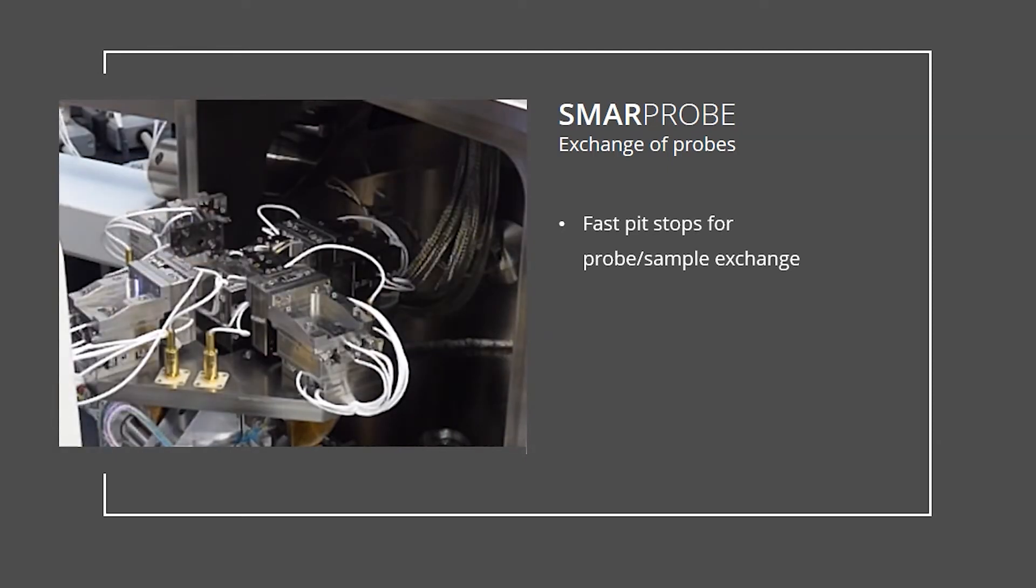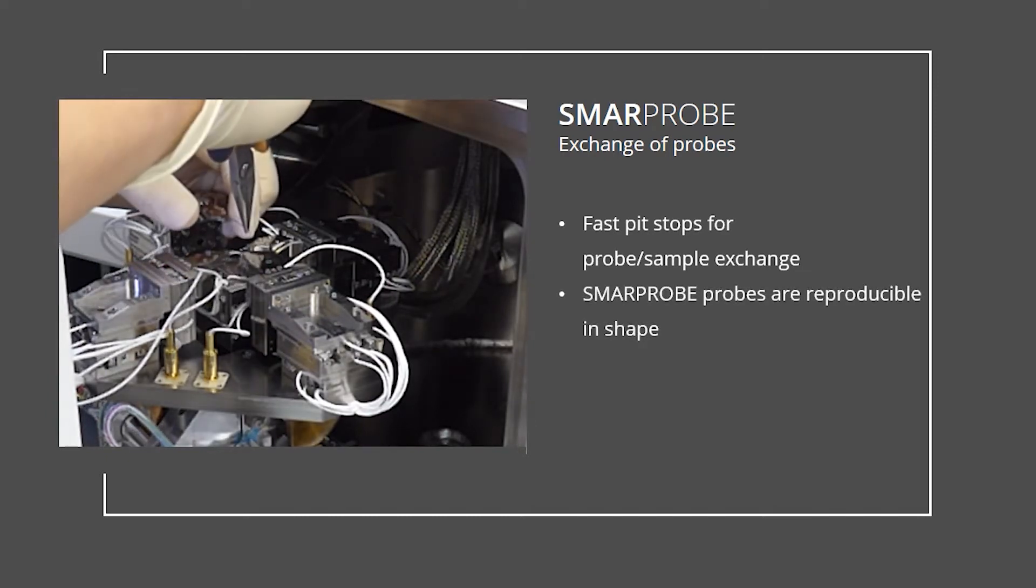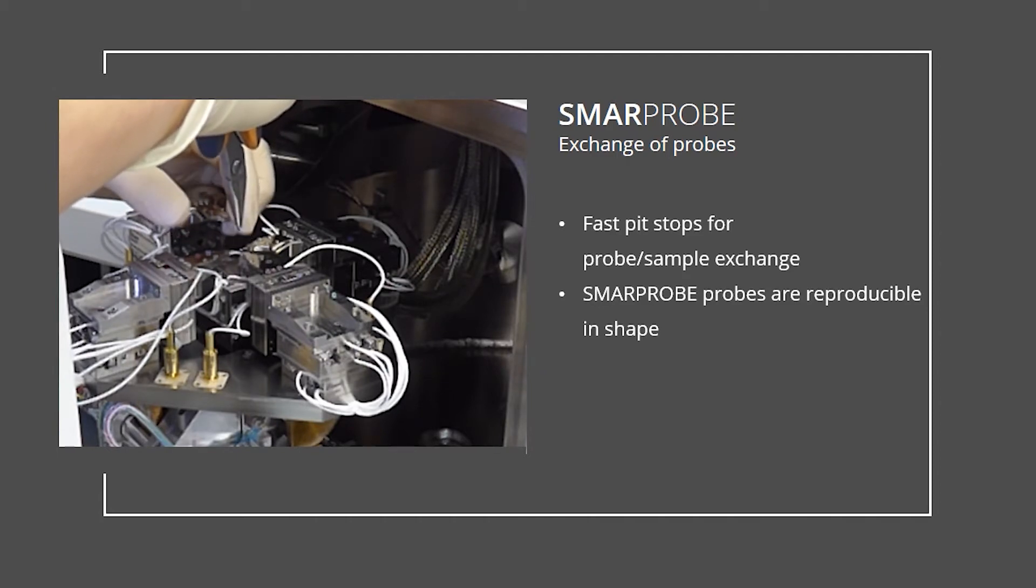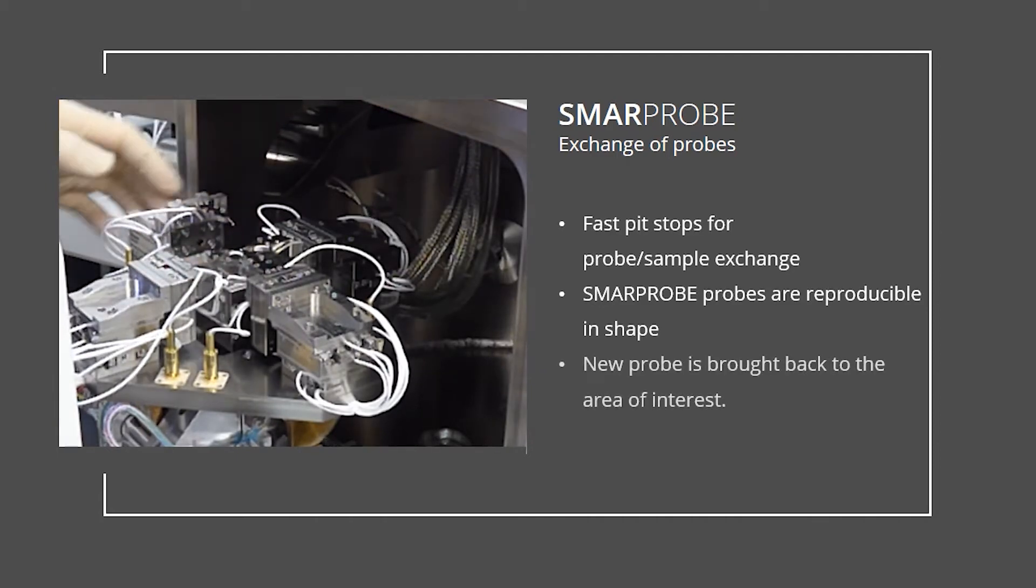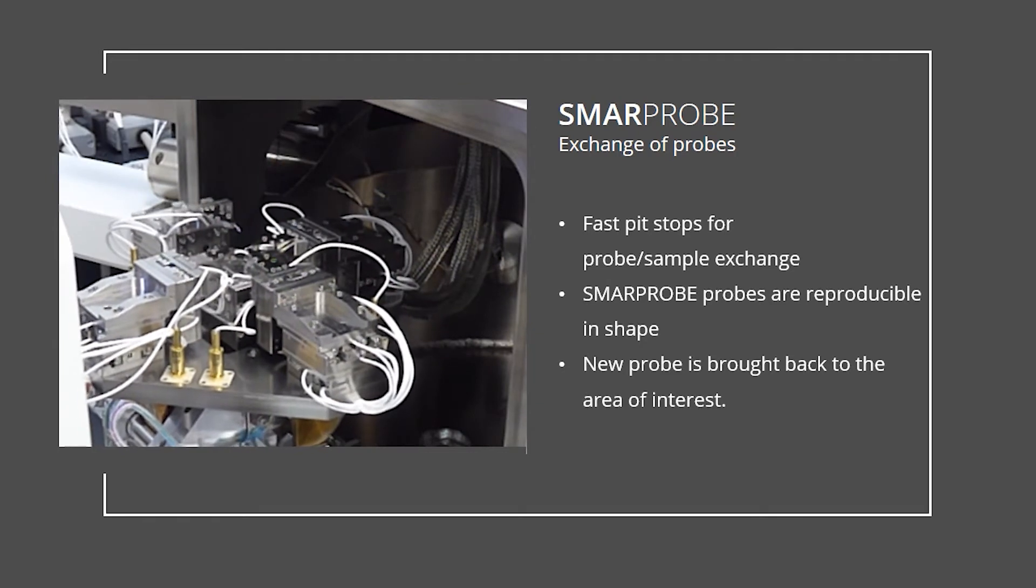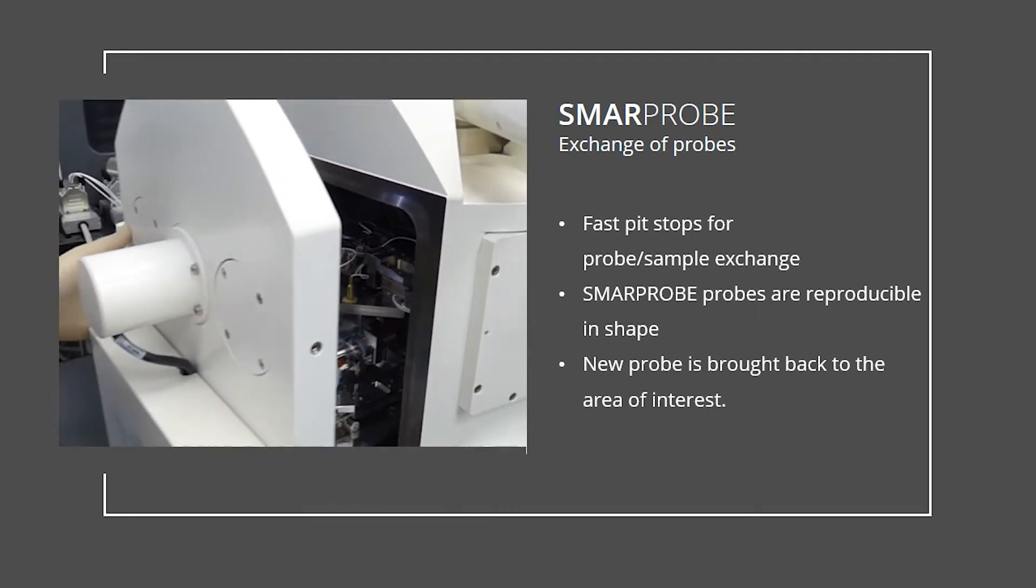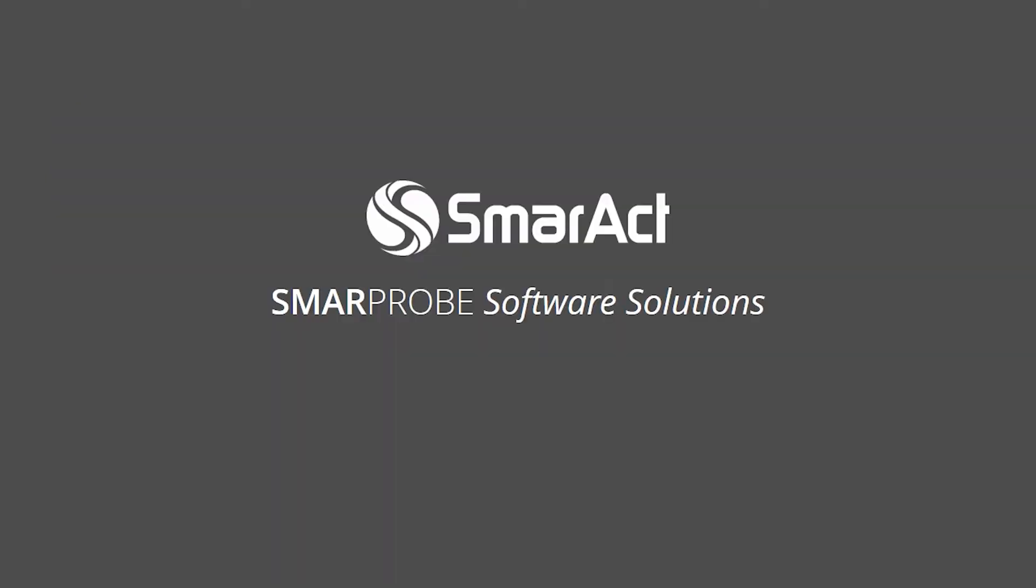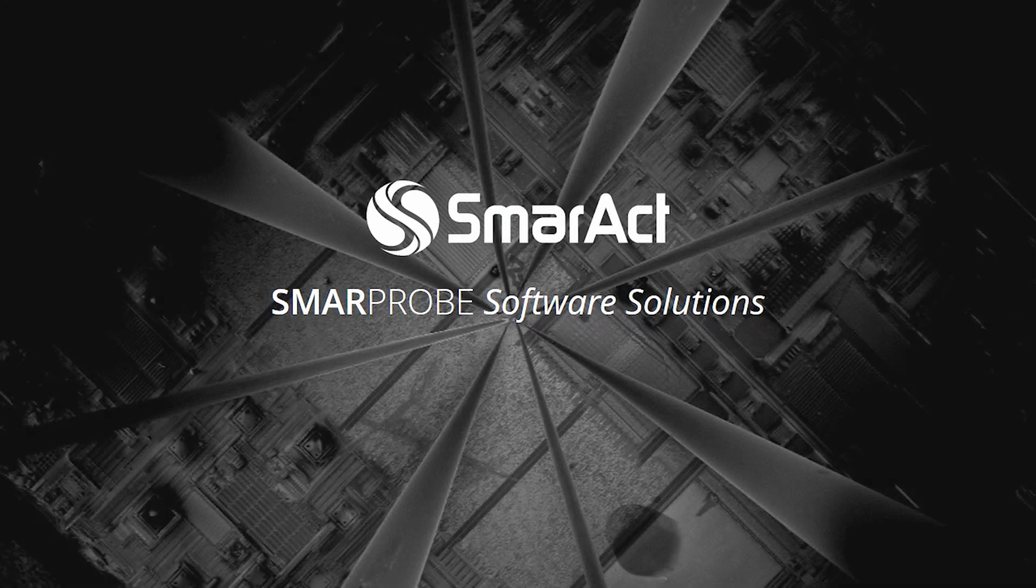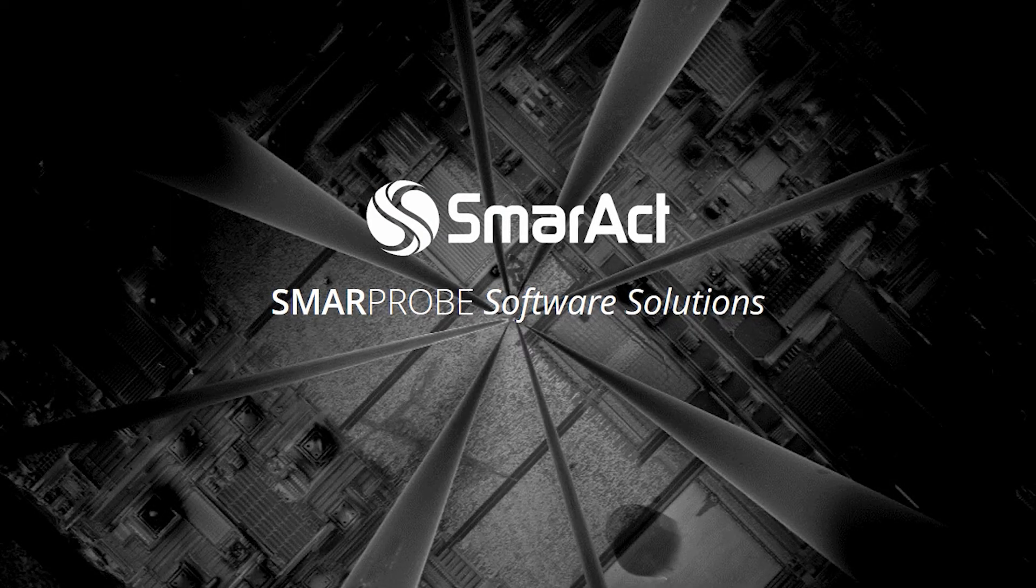The new probe, prepared by the SmarProbe etching station, is marked to allow reproducible insertion. After installation, the motion system brings the probe back to the prior position and probing can continue immediately. This is just one example of how closed-loop motion helps to speed up the process of nanoprobing.